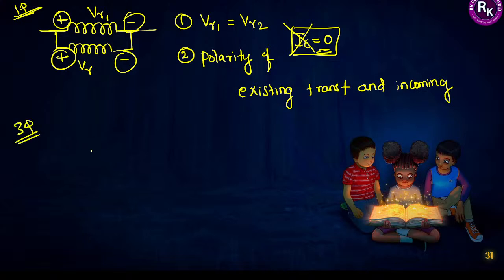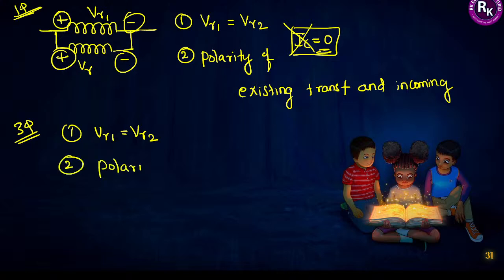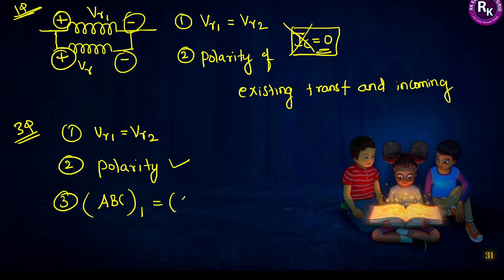Those are the two conditions for single-phase parallel operation. For three-phase transformers, a few more conditions apply. First, rated voltage of the existing and incoming transformer should be same. Second, polarity of both transformers should be same. The additional condition is that the phase sequence of the existing transformer and the incoming transformer should be same — that is very important. If the existing transformer operates in sequence ABC, you must not bring a transformer with sequence ACB.